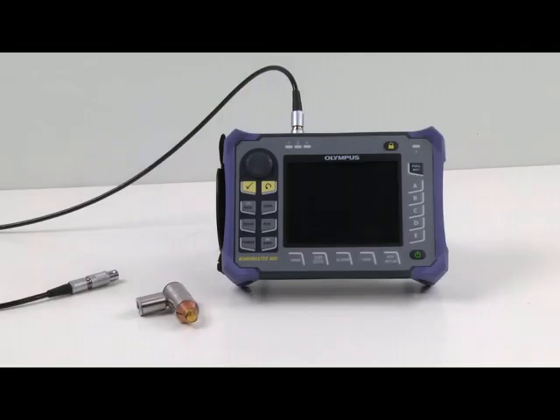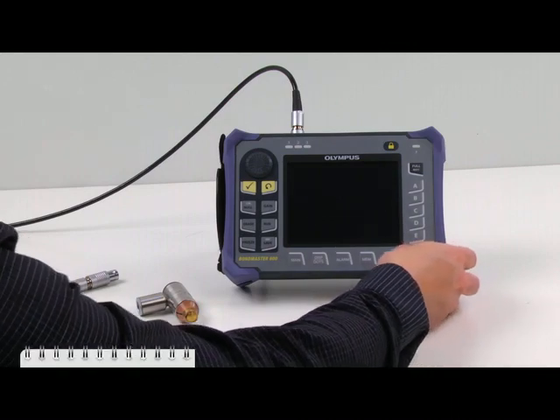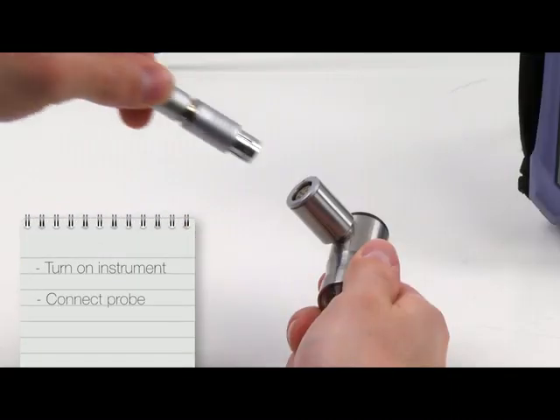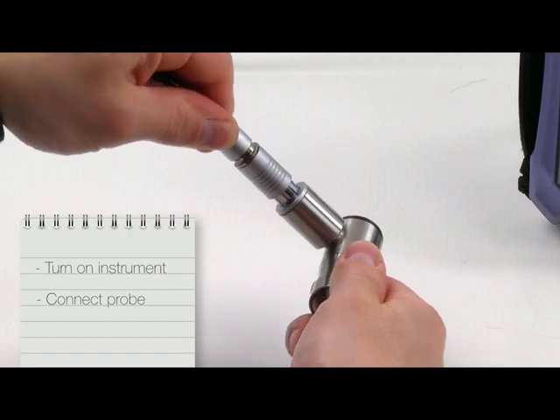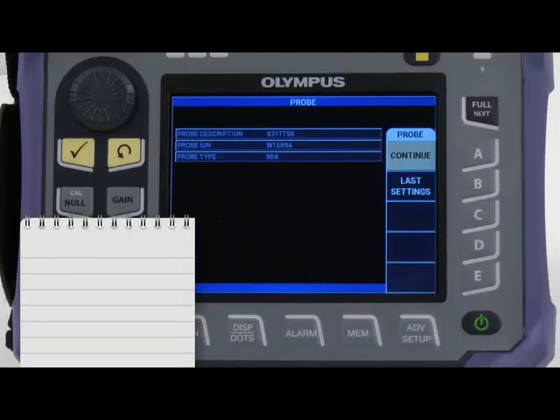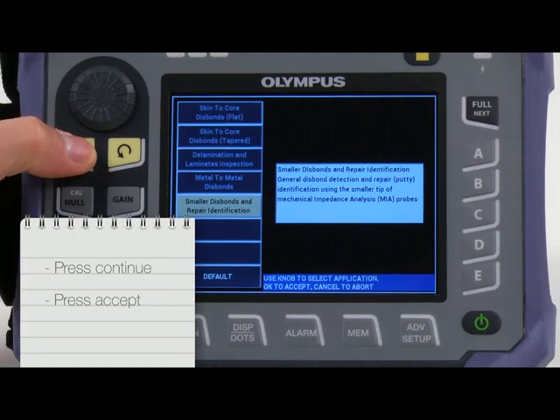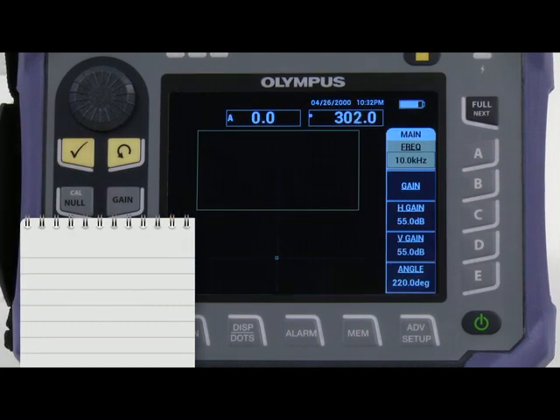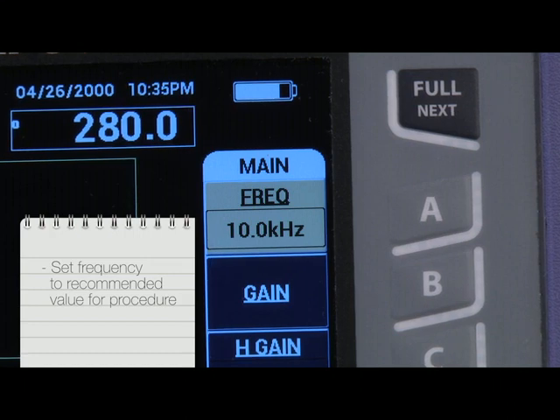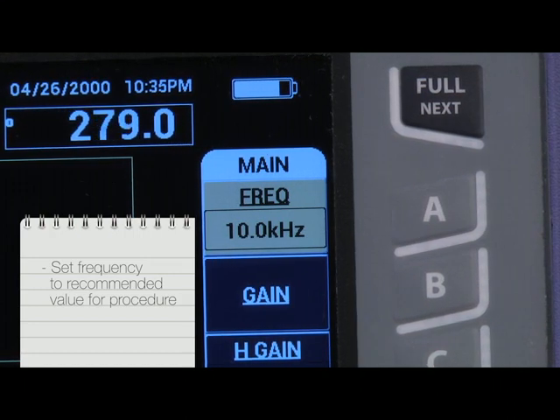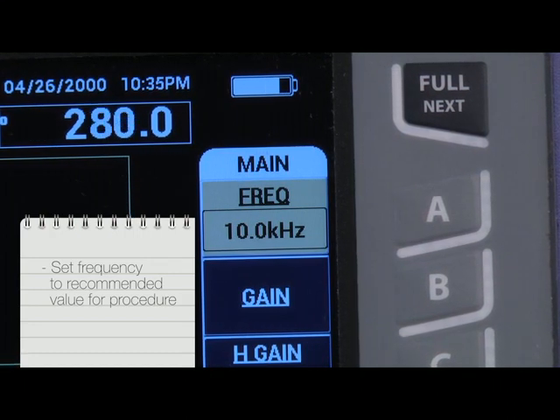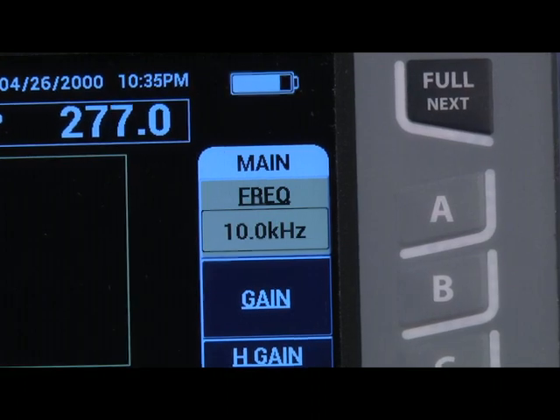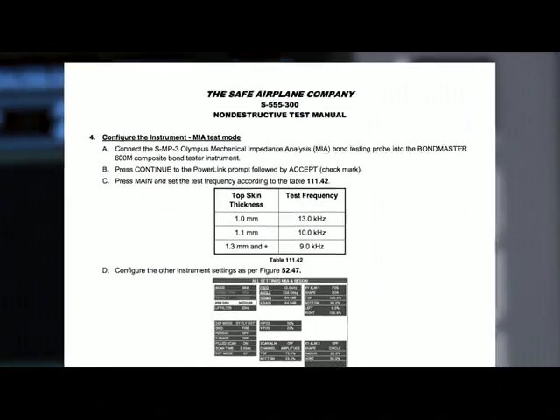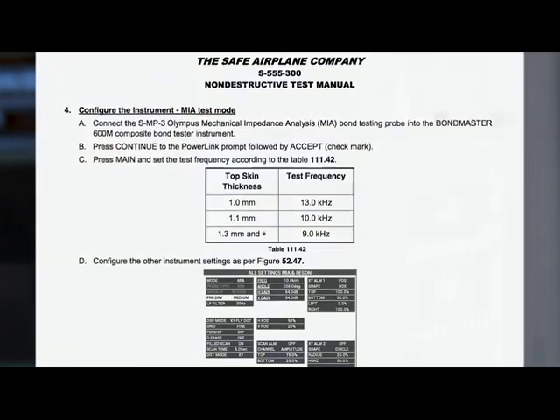For typical inspection procedures, such as inspecting an aircraft component, turn on the instrument and connect the MIA probe. When prompted, press Continue, then Accept to load the default settings. Set the frequency to the value recommended by the inspection procedure. For this video, we will use the default value of 10 kHz. Set any other parameters as needed if required by the procedure.